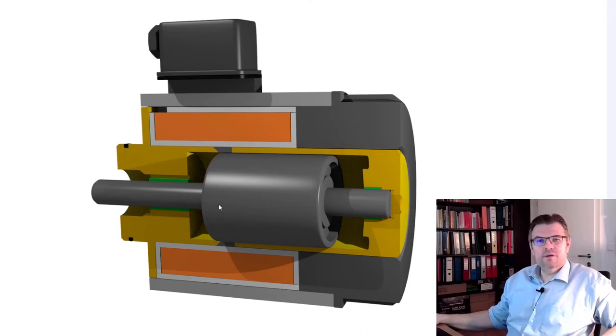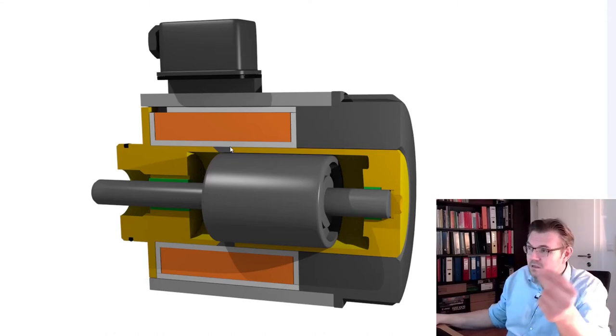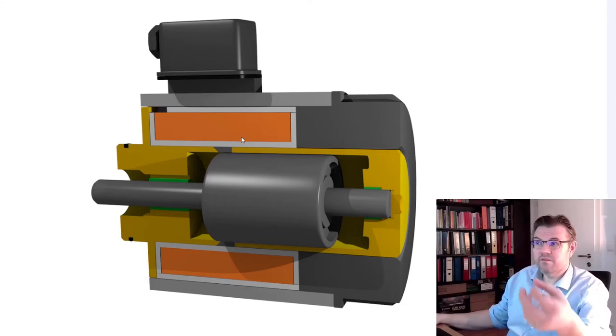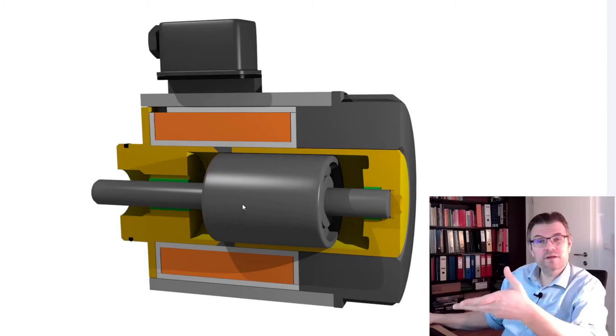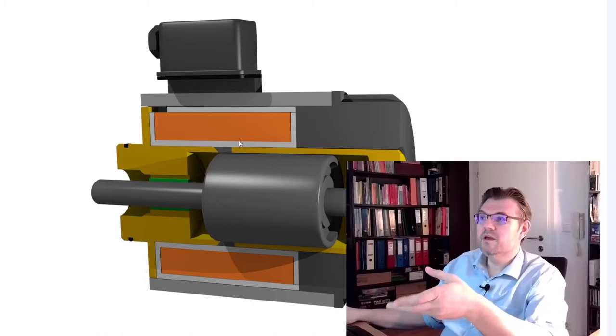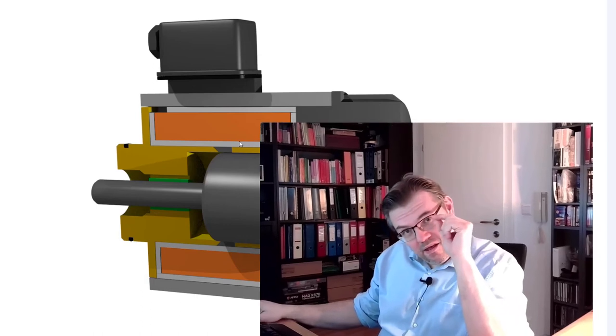So, this movement I can use. In standard switching valves, we only turn it off and on the coil. And this will then push from this side or push from the other side. And this is how an electromagnetic operation of a coil is working. In a proportional magnet like this, it's working pretty much the same way.